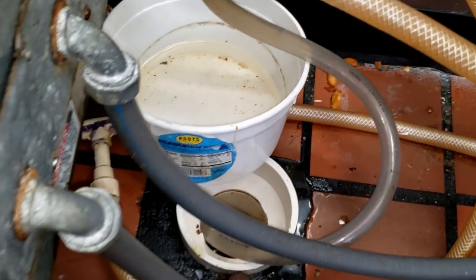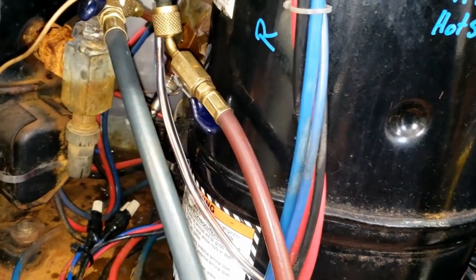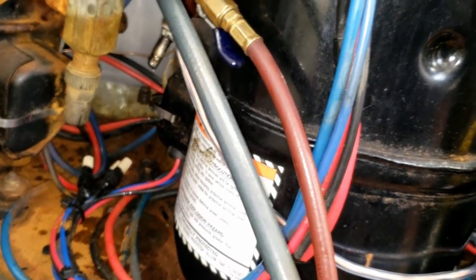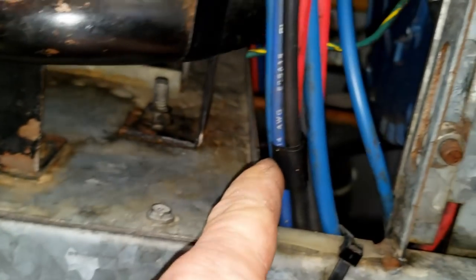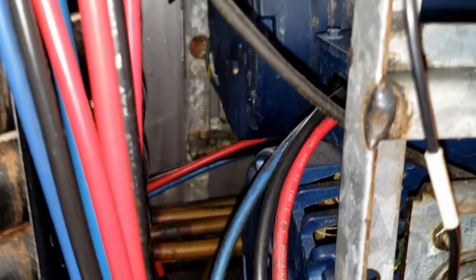That's about it — I'm going to go ahead and move on to this next machine over here. It's got a control board they want to change out because it's cycling too often. They already changed the sensor and they order their own parts and just have us put them in sometimes, depending on what it is. We're going to get that put in now and double-check for any wires that might be rubbing on things, because it happens with these machines quite often.